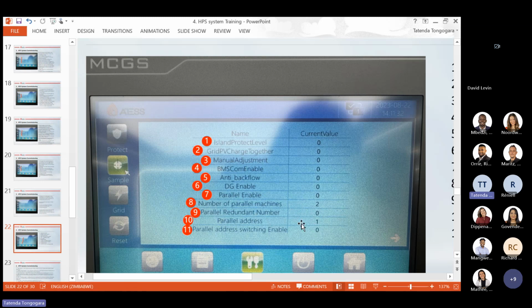But if the load is 90 kilowatt, 95 kilowatt, one of the inverters will take the load. And then parallel address. The master should have the parallel address 1, the slave 2, should have 3, and then the last one should take parallel address of 4.